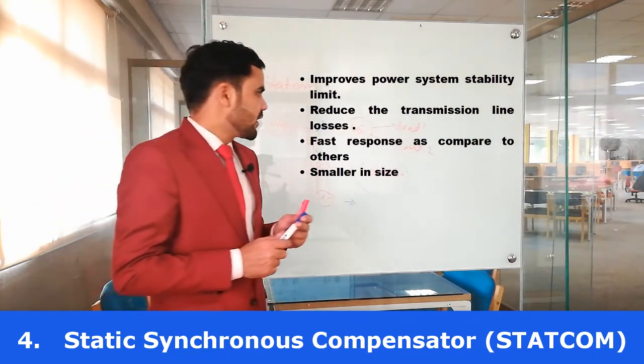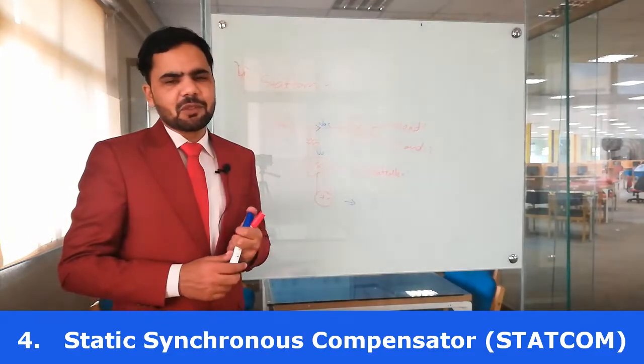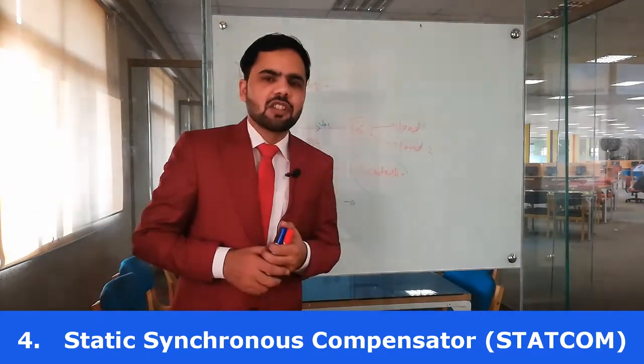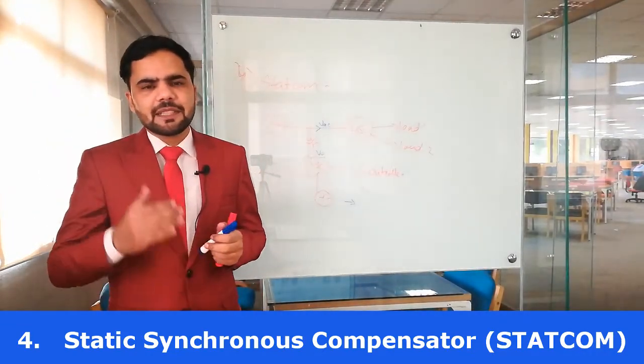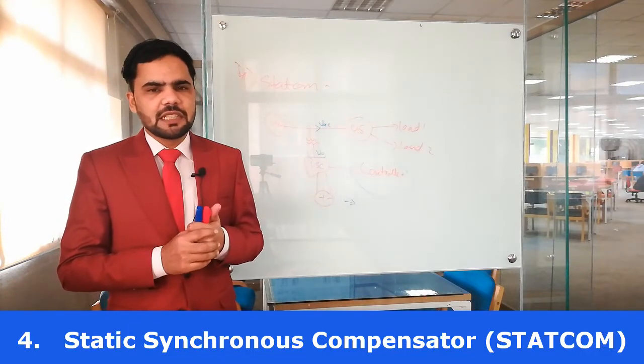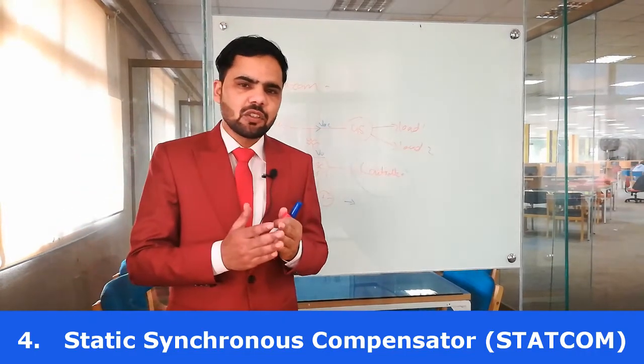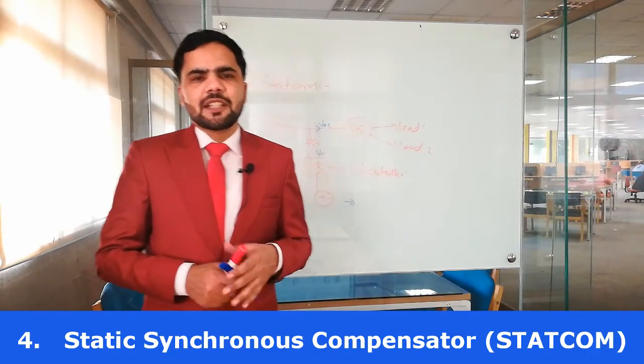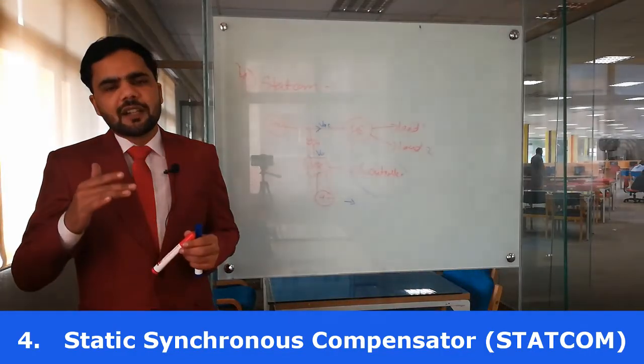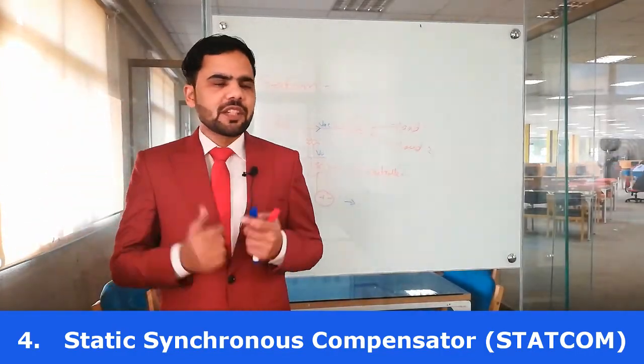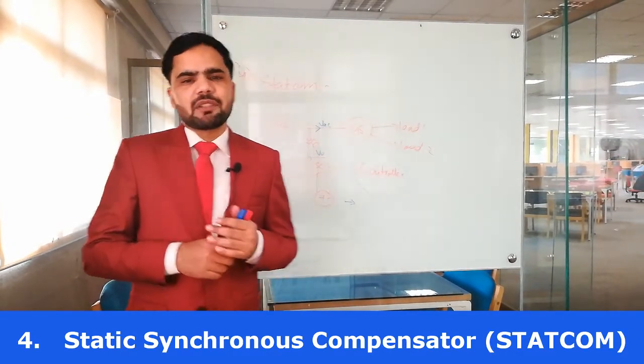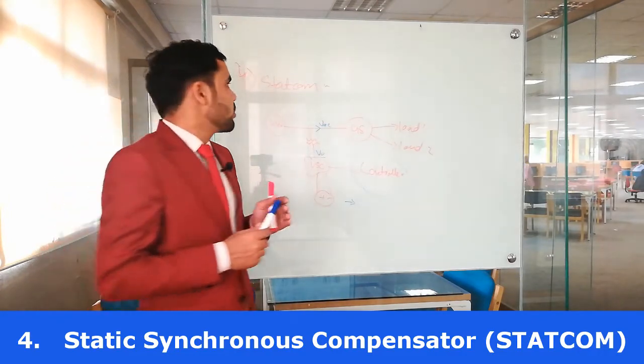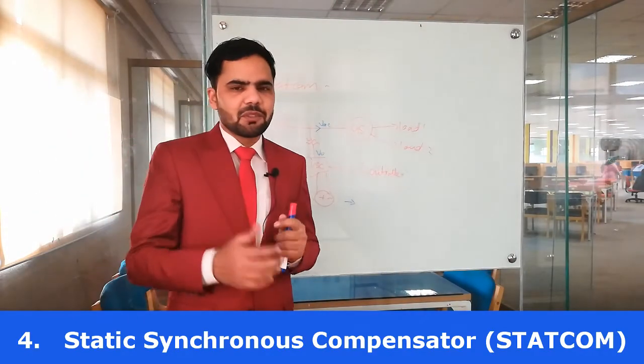This is another important type of the FACTS device that is very commonly used for transmission of power from the generating station to the load. The best location for using the STATCOM is in the center or toward the grid side, because under varying load conditions, it should be able to provide or absorb the reactive power according to the requirement of the power system.